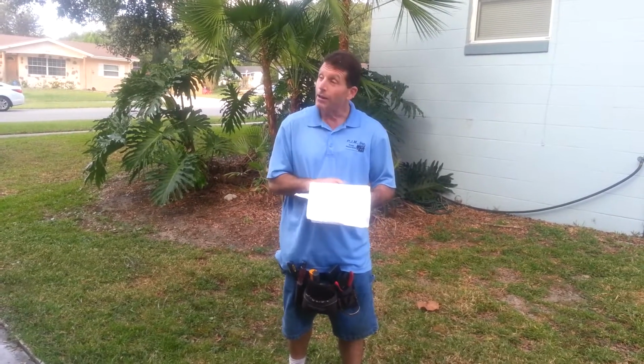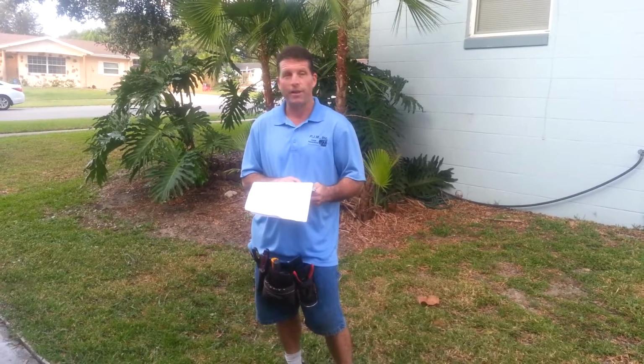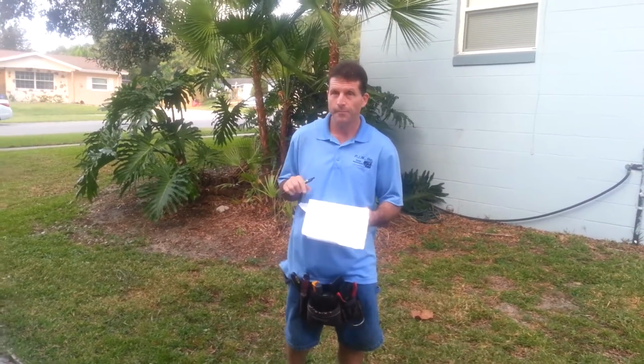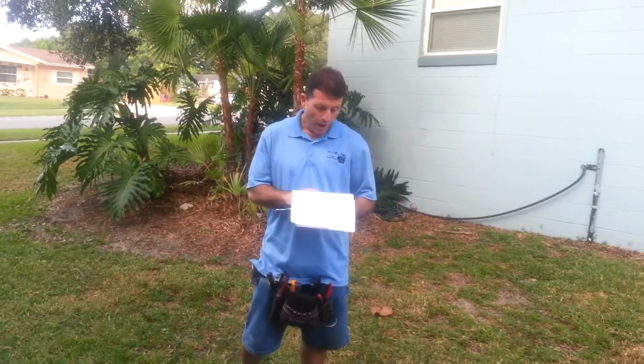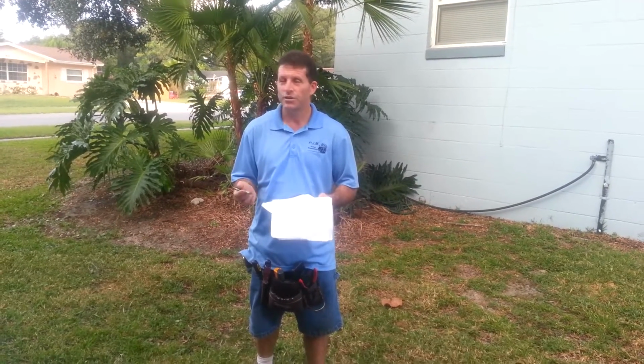Right. That you would want to pay attention to for FHA, because they usually look for obvious stuff like that. Like exposed wires, even cable wires, I would terminate them, that are terminated but just hanging there. Other examples of this are like the panel legend is not labeled clearly, so you don't really know what anything is controlling.